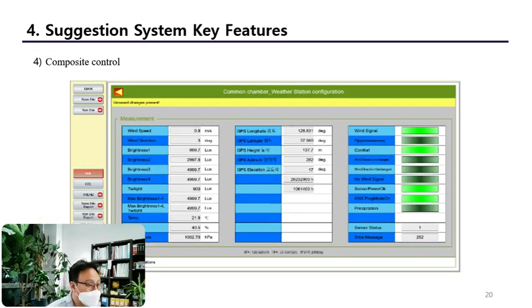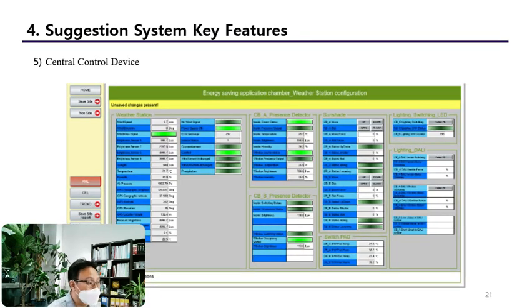Through the interacting controller, various sensors and control items can be set, and picture 8 shows the composition control setting UI. Working with the BEMS system, energy saving can be achieved by the complex control system in the building, and flexible control is possible through the linkage of composition load based on real-time power and energy measurements and field sensor data. Picture 9 illustrates the UI of the SCADA system.